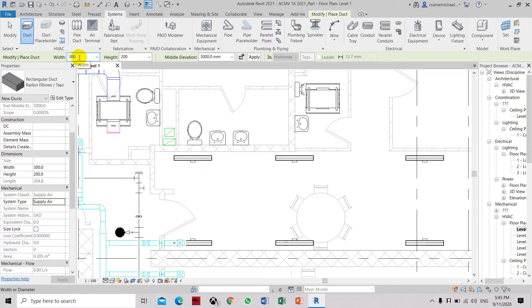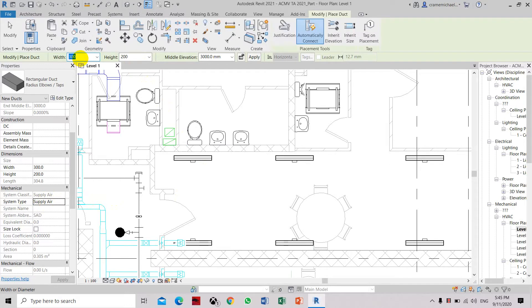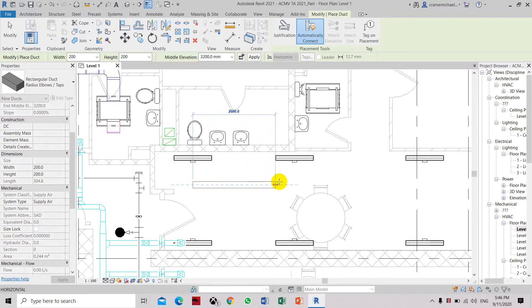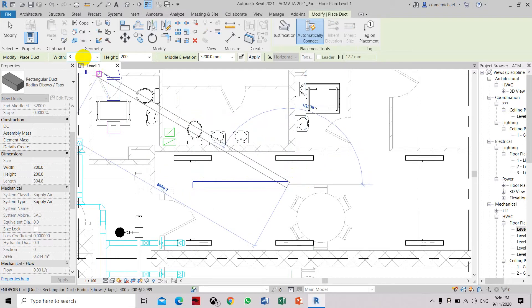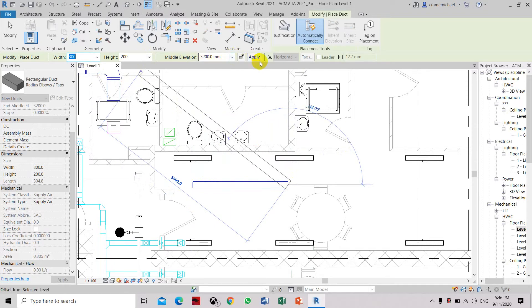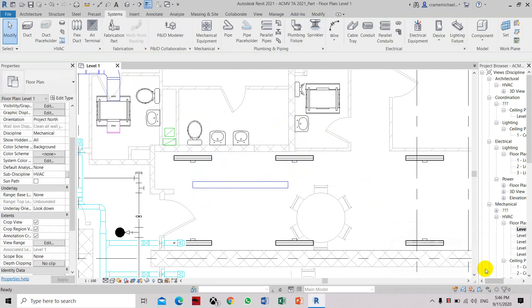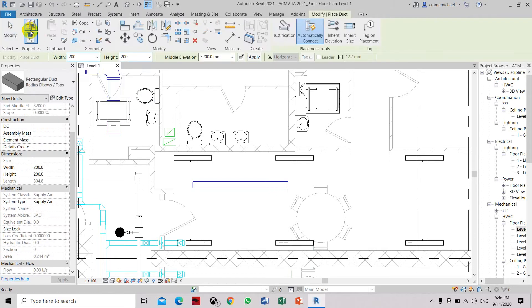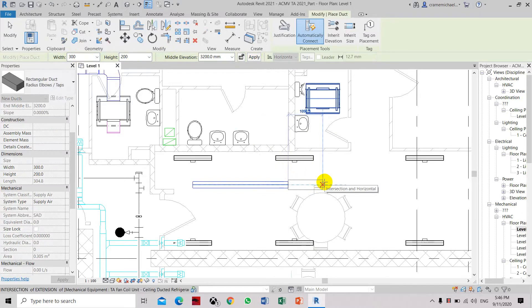At the top you can set the duct width and duct height. We can use 200 by 200. The middle elevation is the elevation of the duct at the center of the duct in reference to the floor level. Our ceiling is at 2.8 meters so we can set the duct elevation to around 3.2 meters. Click Apply and start drawing the duct. From here we increase the duct size to 300 by 200, maintain the elevation, click Apply, and continue routing until the centerline, then turn.